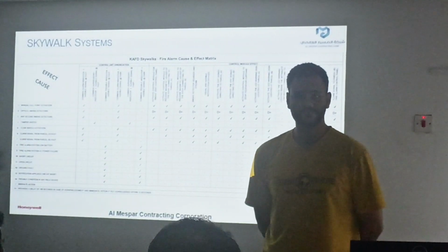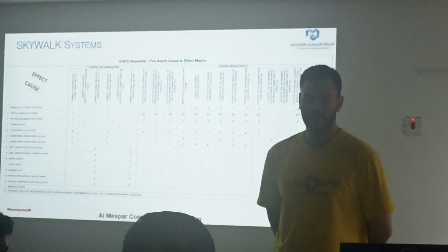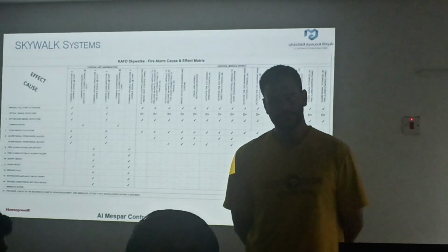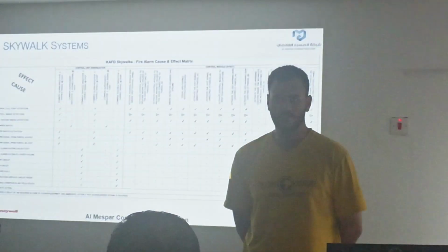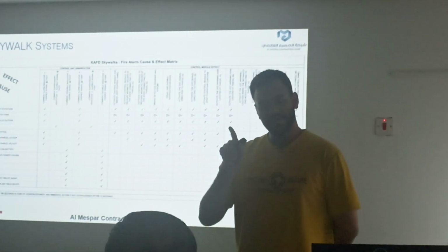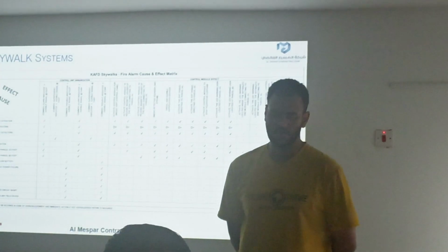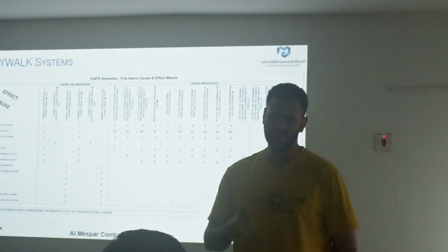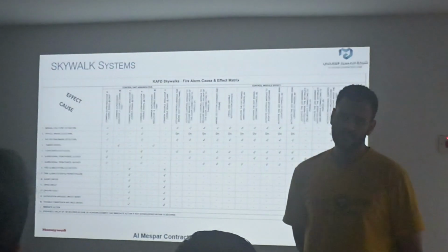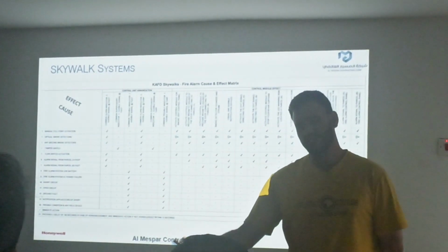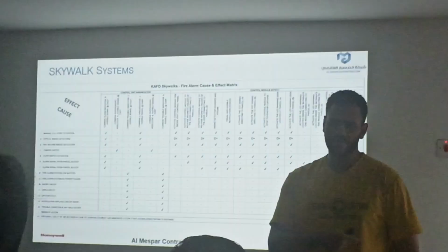You said all FCUs, fire curtains, everything will be shut down inside the skywalk. Then do we need to turn them on manually, or will they be turned on automatically? If you make a reset, it will be turned on automatically. Yes, all devices connected to MCC, which are FCU, fresh air fan, and air curtain. And the pumps are also connected. The pump will run if the FCU is running and there's water coming, then the pump will run automatically.